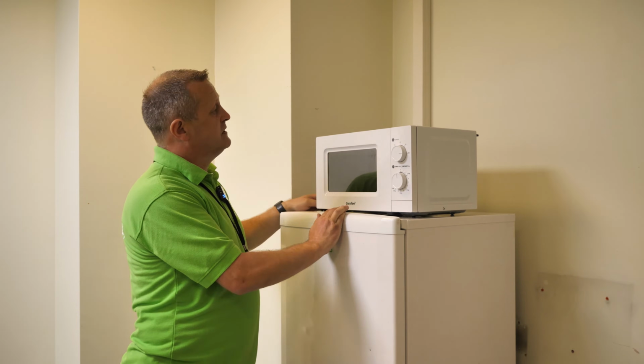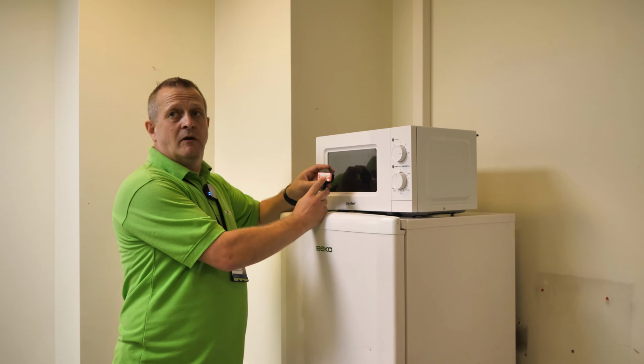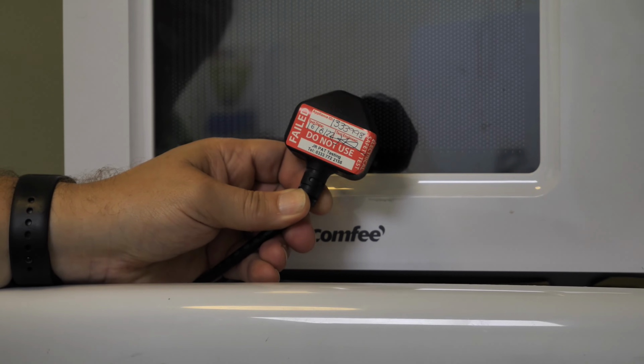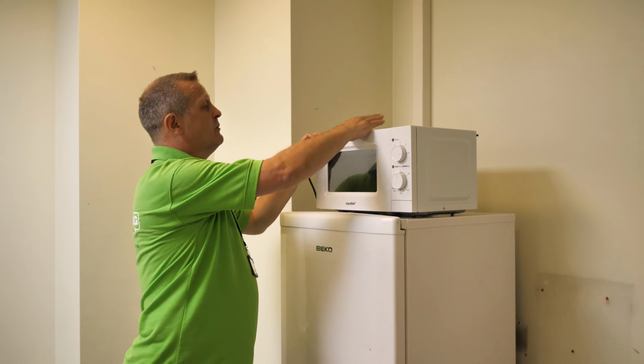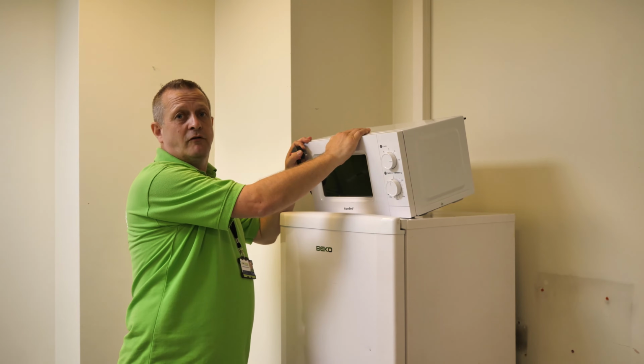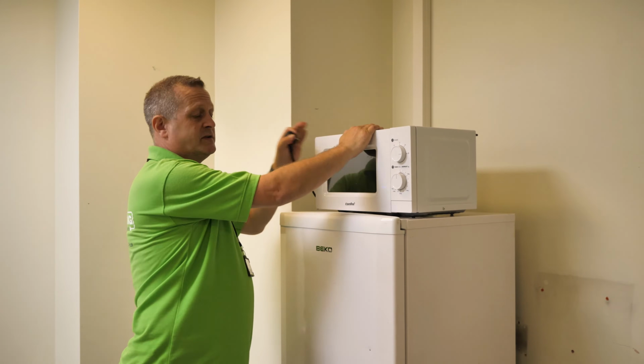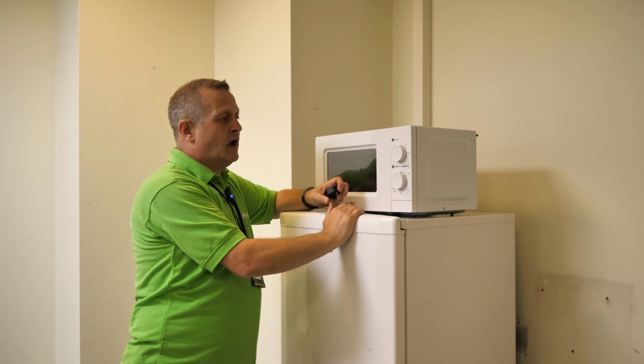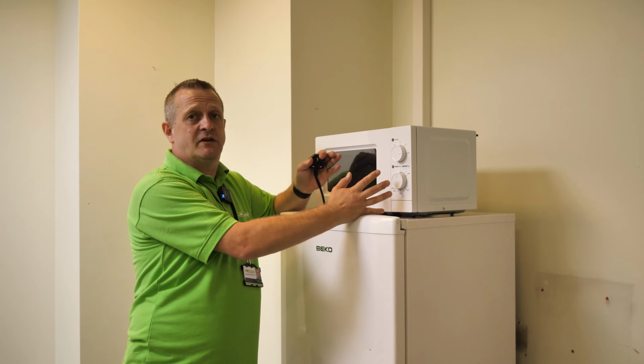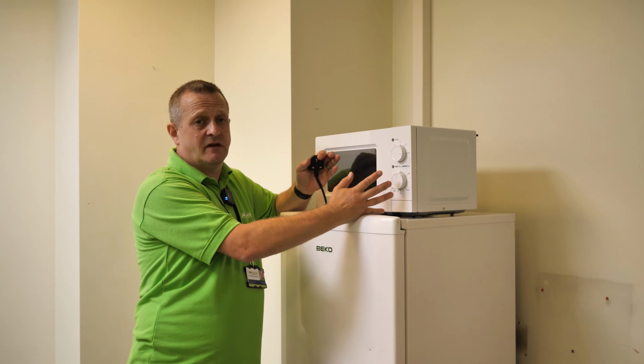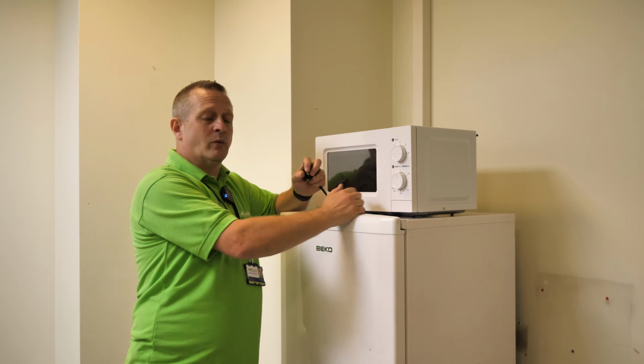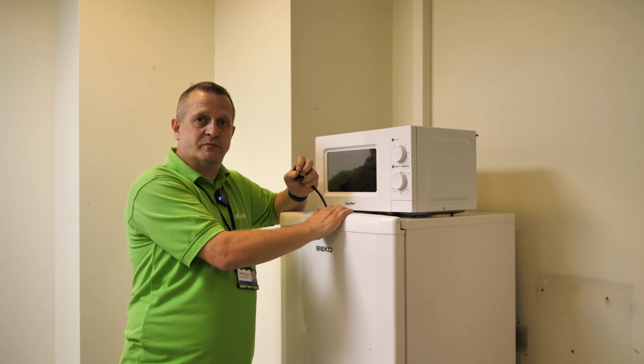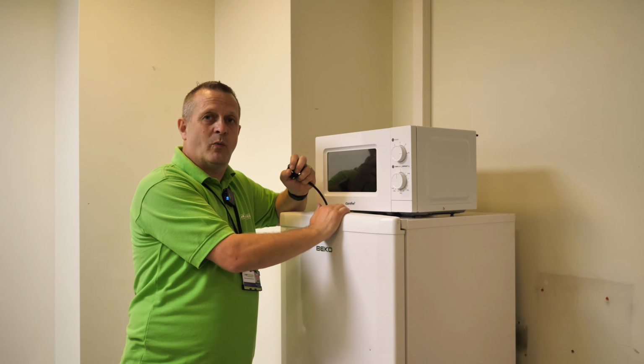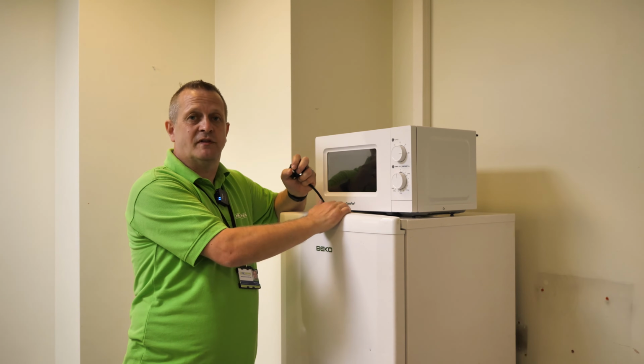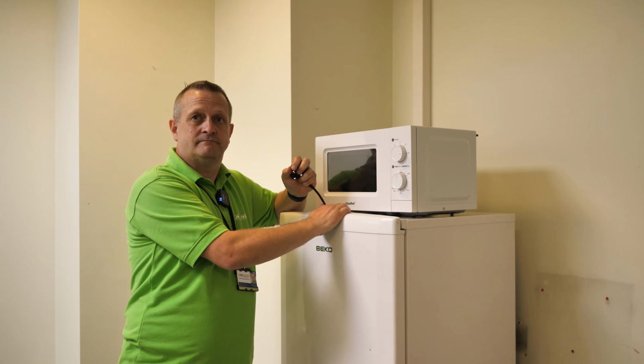So what we're going to do is mark it up with a red failed label on the plug, and I've also put another red failed label on the top of the appliance, so it's very clearly marked. This microwave now needs to be taken out of service as it's technically dangerous, and we will inform the responsible person that we have taken this out of commission and they are to dispose of it.